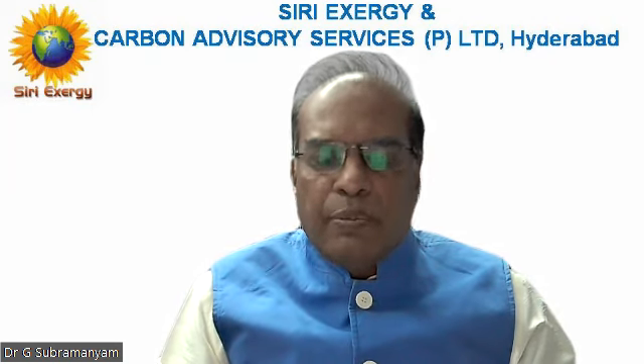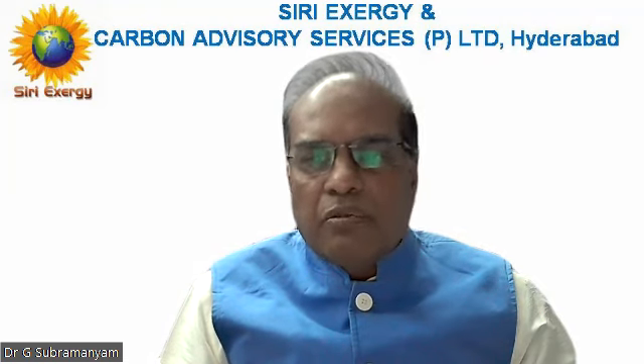From all these experiences, we can say that the specific water consumption maintained, even in NTPC plants, varies from 1.6 to almost 8 liters per kWh in some places. Again, this depends on the size of the unit and on whether it is a gas plant. A gas plant normally has a low specific water consumption because there is no ash handling. Similarly, with a once through system there is no cooling tower, so the specific water consumption varies again. In some plants like NTPC Dadri, there is only dry ash handling, so there again specific water consumption is lower. So there is a lot of variation.